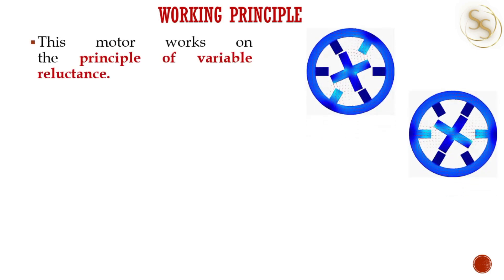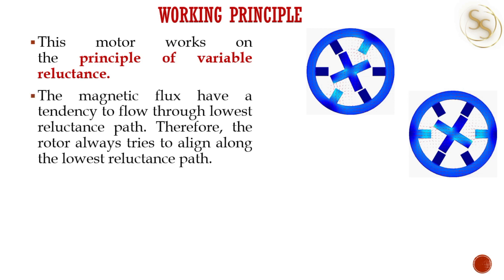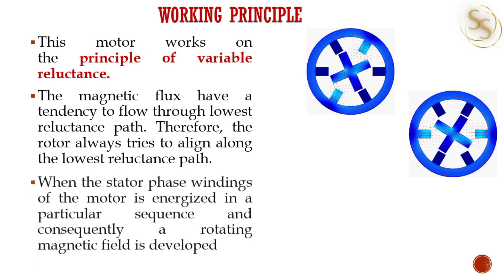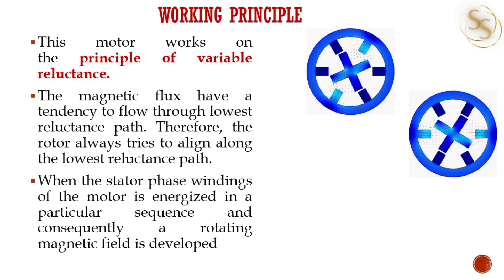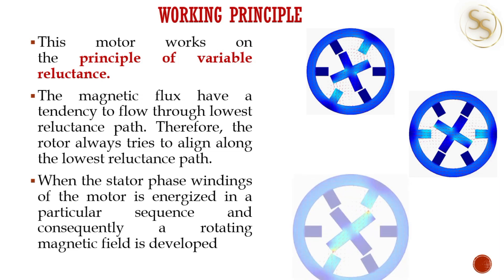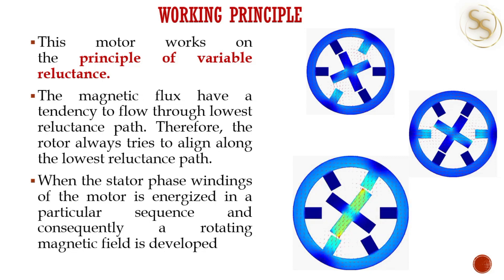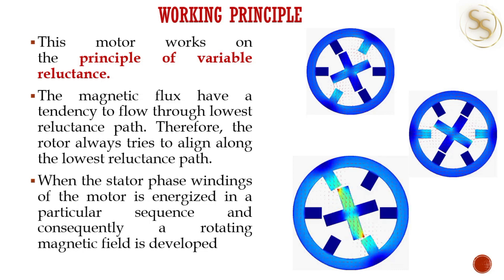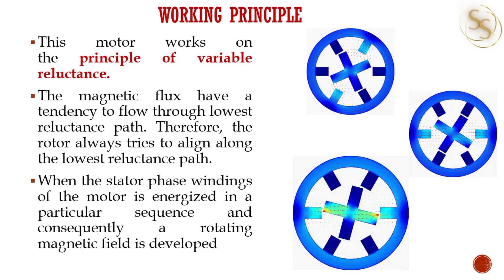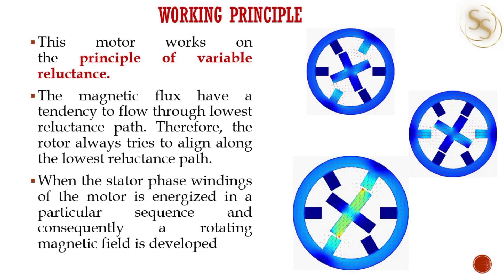A switched reluctance motor works under the principle of variable reluctance. The magnetic flux has a tendency to flow through the lowest reluctance path. When the stator phase windings of the motor are energized in a sequence, it will produce a rotating magnetic field. You can see the two pictures given at the right side here, which show the magnetic flux path between the stator and rotor.